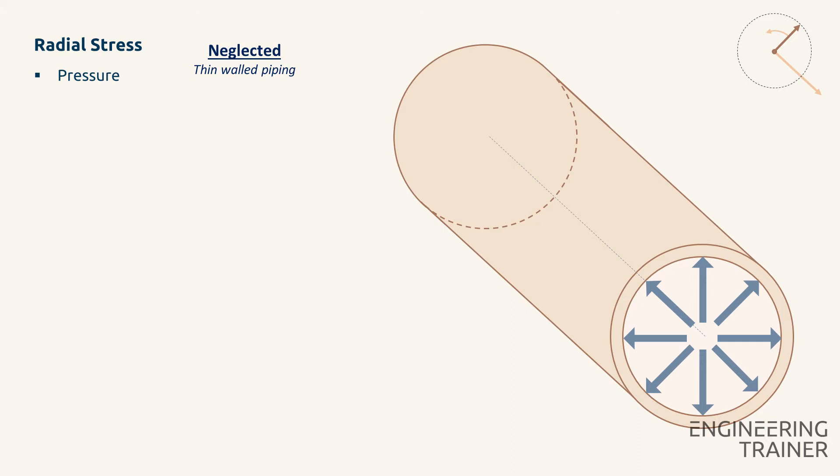It is important to realize that only the pressure load causes an overall radial stress in our piping geometry. No other load will result in such an overall radial stress. It is only the pressure load that contributes, and we already concluded that this contribution can be neglected, so we will set it to zero.